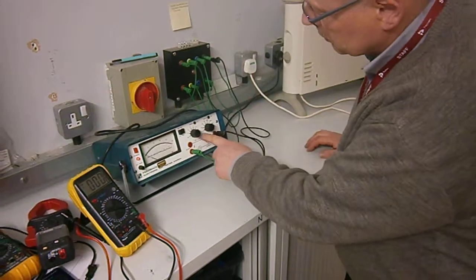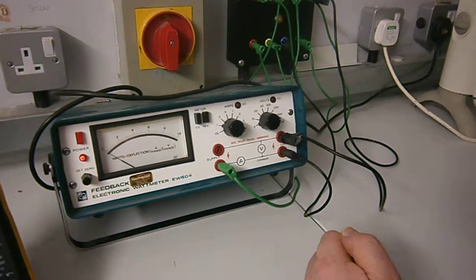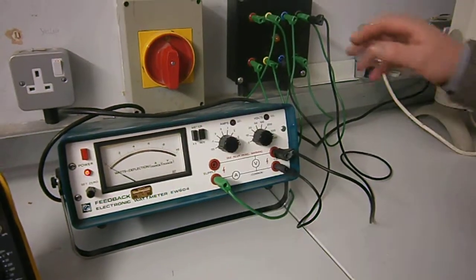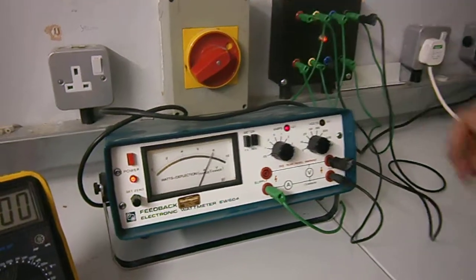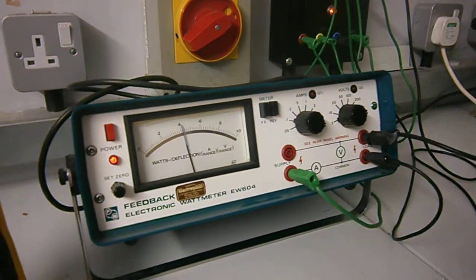And I've set on 10 amps here, 500 volts, which is what we'd expect because this will draw more than 5 amps. If I put it onto 5 amps and switch on for a minute you'll see that we get a display that doesn't go off the end but we do get the overload light coming on so I'm going to put it onto the 10 amp display.